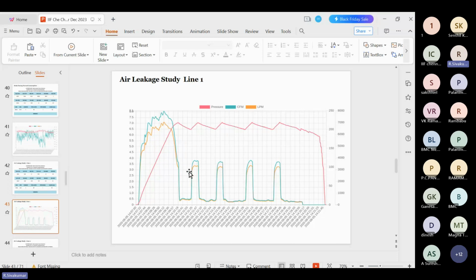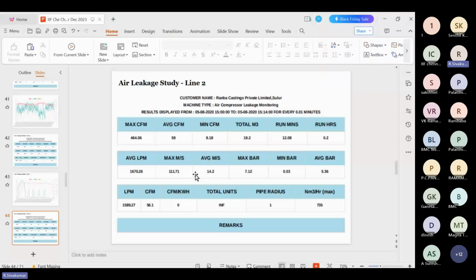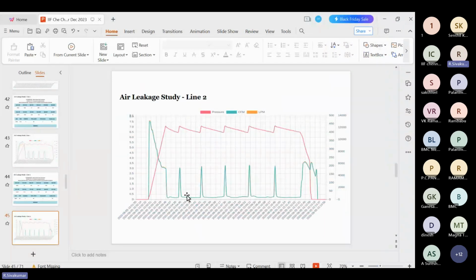So how much CFM air leakage is there? And if the kWh meter, the energy meter, is incorporated, the unit can exactly quantify the energy loss in terms of CFM and in terms of kWh. Similarly, this is the air leakage study in another line, line 2, in the same foundry. Here in line 2 the leakage is minimum, whereas in line 1 the leakage is high.